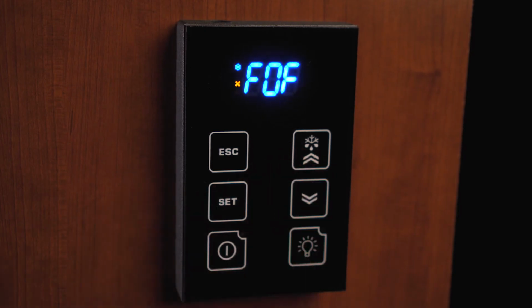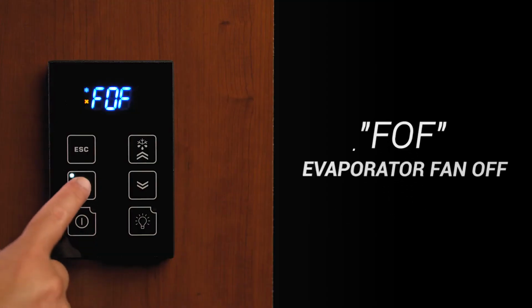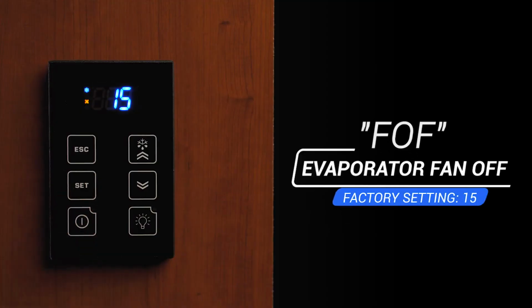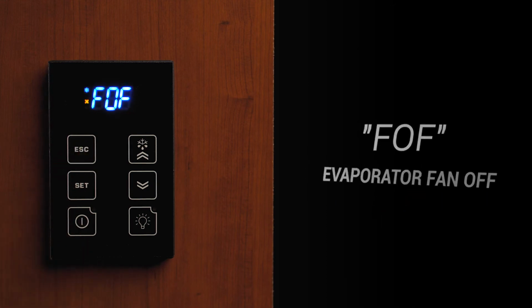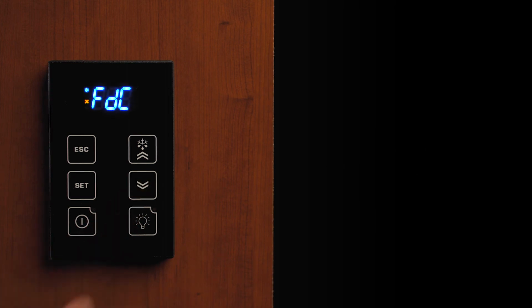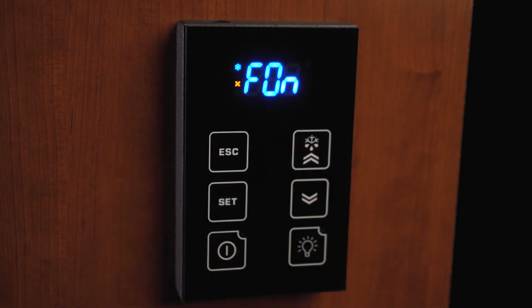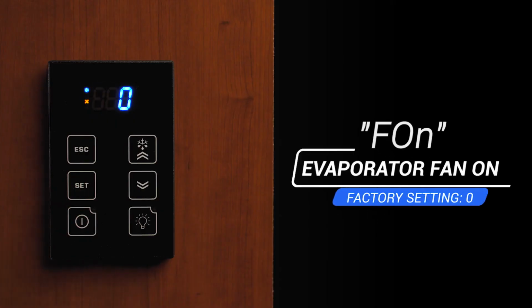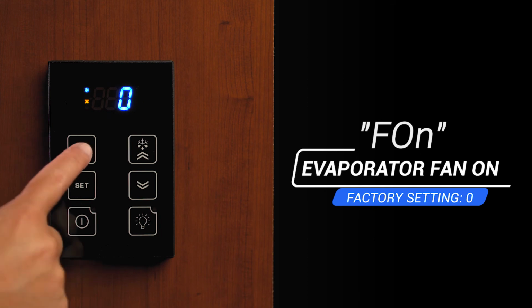FOF is for the evaporator fan off. It is factory set at 15 and it is not recommended to change it. Using the FDC setting will accomplish having the fan run after the cooling cycle if needed. FON is for the evaporator fan on. This is factory set at 0. Using the FDC setting will accomplish the same result.